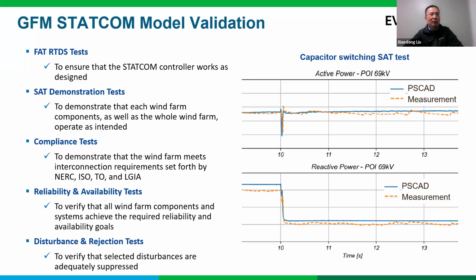It's limited to the controller and the protection hardware only, not the STATCOM equipment itself. And the grid model and the wind farm model are highly simplified in the RTDS because of limitations of the simulation platform. The SAT test, that is the site test, is the best opportunity to demonstrate that our wind farm devices, one by one or operating as a whole, operate as expected on the different operation topologies and changeovers, including single device switching, energization, control step change, and control mode change. All measurements are recorded and compared with PSCAD simulations in the South Fork site test.